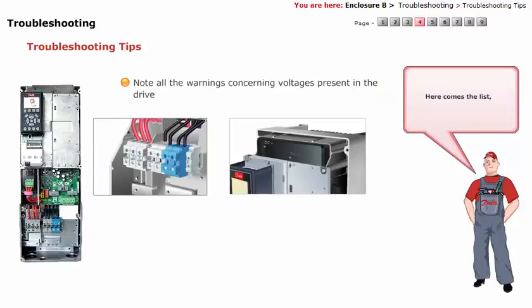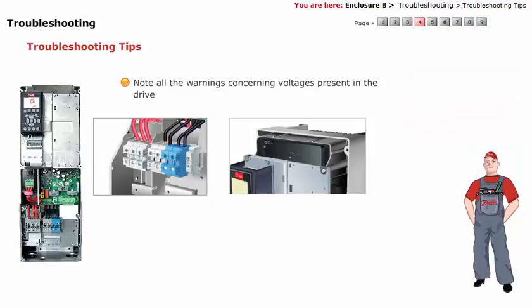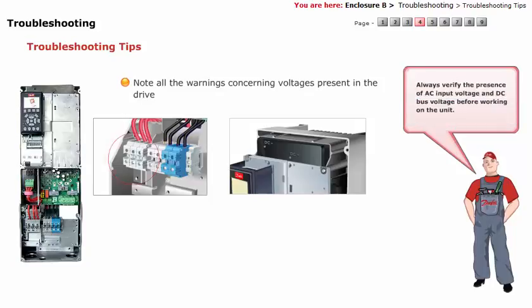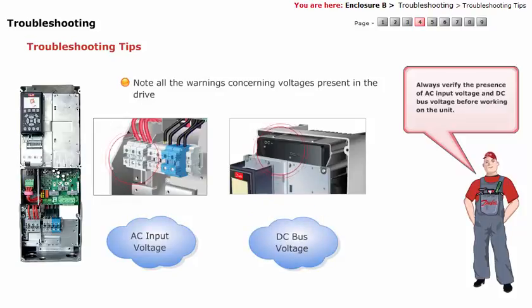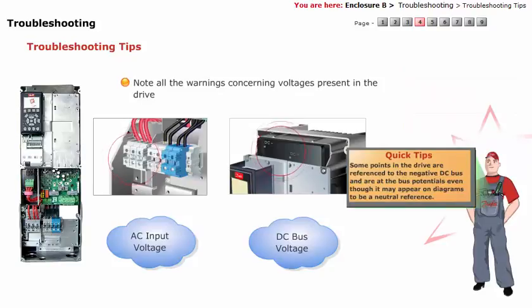1. Note all the warnings concerning voltages present in the drive. Always verify the presence of AC input voltage and DC bus voltage before working on the unit. Some points in the drive are referenced to the negative DC bus and are at the bus potentials, even though it may appear on diagrams to be a neutral reference.